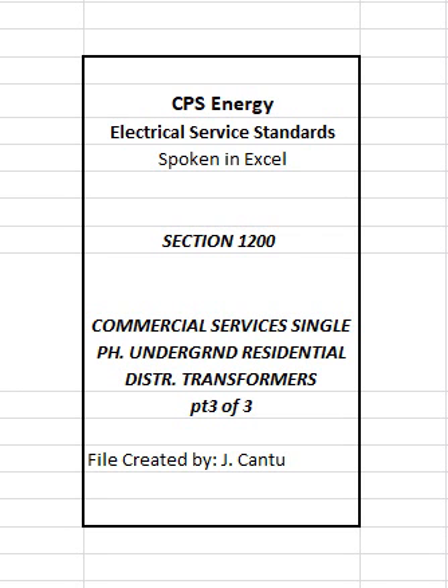For transformer and pull box that are to be installed in public ROW, the customer shall provide written approval from the AHJ and shall install the transformer within 10 feet of the meter location. Customer shall furnish a site plan or drawing to CPS Energy that establishes the exact location of the transformer slab, and any required pull box slabs, with respect to permanent and identifiable structures. The location shall provide for the following.